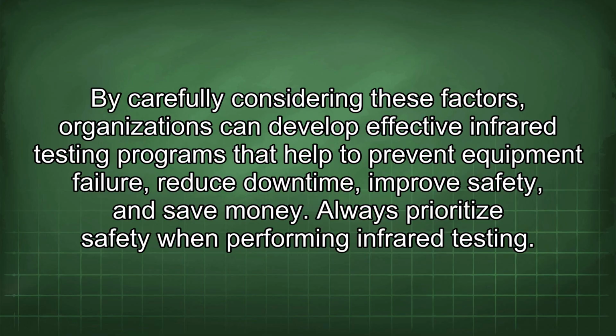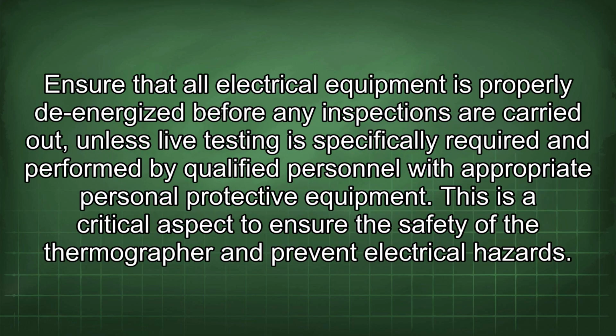Always prioritize safety when performing infrared testing. Ensure that all electrical equipment is properly de-energized before any inspections are carried out, unless live testing is specifically required and performed by qualified personnel with appropriate personal protective equipment. This is a critical aspect to ensure the safety of the thermographer and prevent electrical hazards.